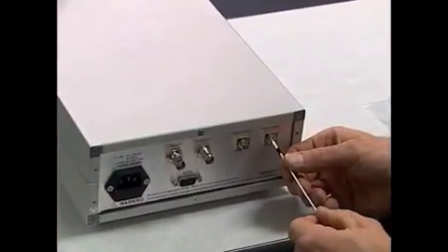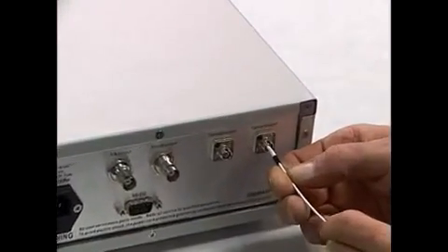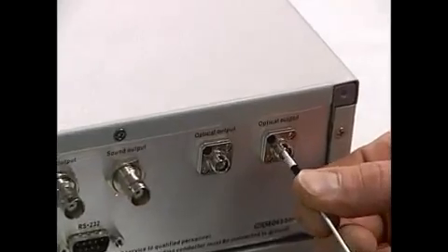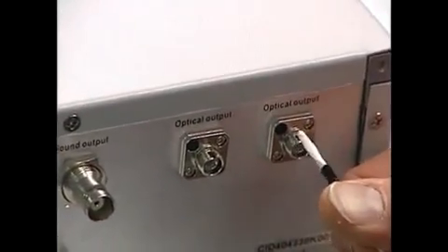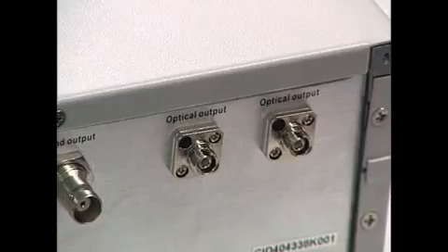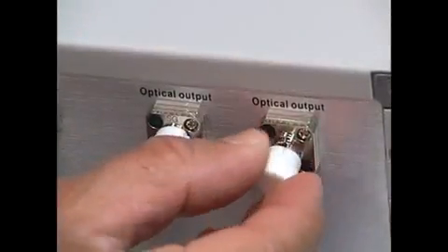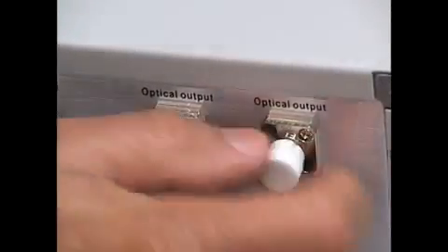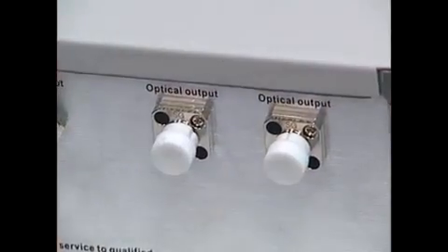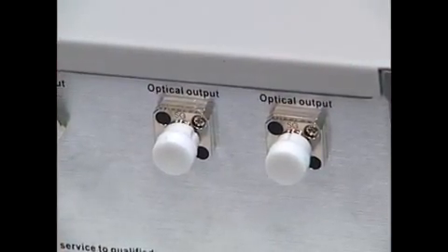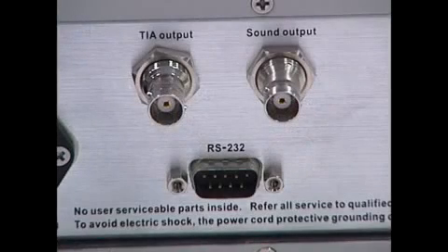It is recommended that the optical ports be cleaned prior to each use with a cleaning swab designed for fiber optic connector ports. Do not use conventional cotton swabs in this application, as they contain oils that will attract airborne contaminants. When not in use, the optical ports must remain capped. The RS-232 port and BNC ports on the rear panel of the instrument are for factory use only and must remain unconnected.